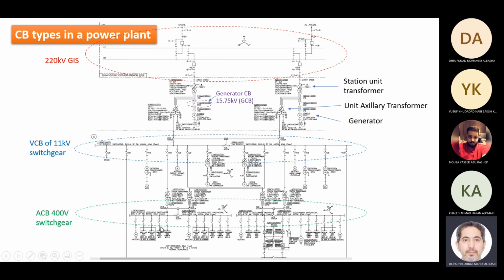At the low voltage level, this 11 kV is also stepped down by transformers. So we have 400 volt line-to-line voltage, and then it feeds the motors, lighting, all the services. Because this is low voltage, 400 volt, we call this 400 volt switchgear, or sometimes a switchboard. Here we use, let's say, ACB breakers at low voltage, but here is vacuum circuit breaker, and here gas insulated switchgear or breakers, SF6.